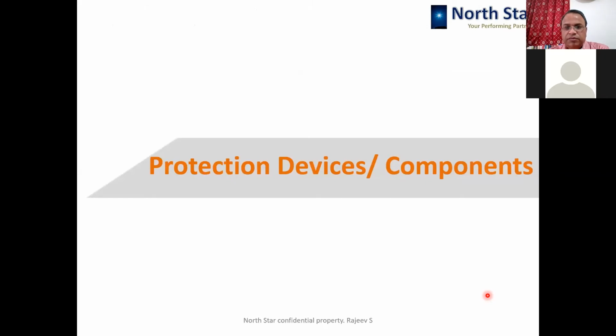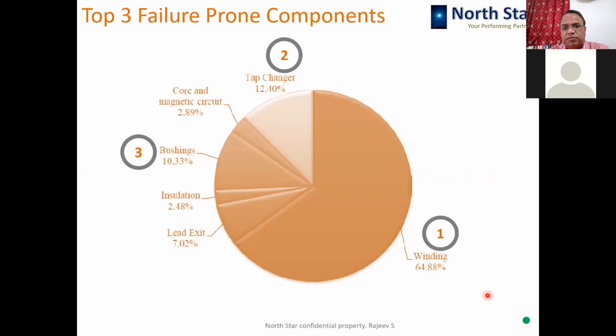Okay. Now coming to protection devices and other components, these are the top three failure-prone components in the transformer. Number one is the windings, of course, because everything comes ultimately on the winding. So winding failure is highest, that is 65%. But winding failures are not attributed only to the winding. There are several other factors, as I said, which contribute ultimately. Because those factors are ignored, the ultimate stress or impact comes on the winding, and the winding has to fail at the end.